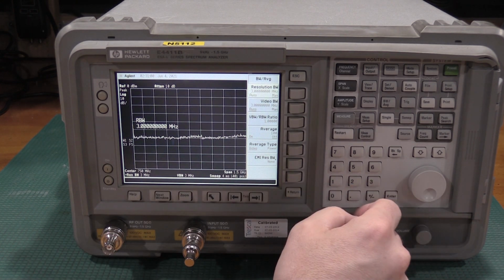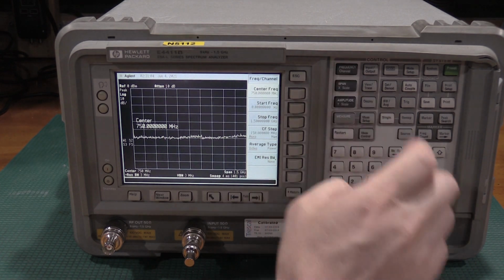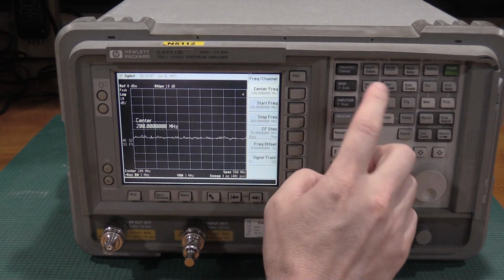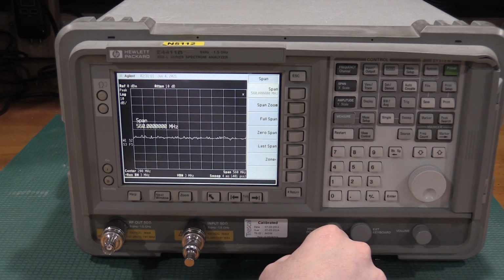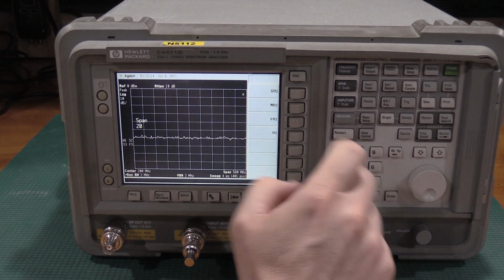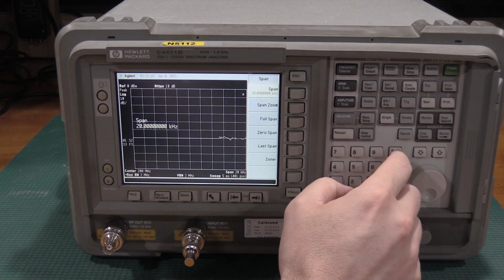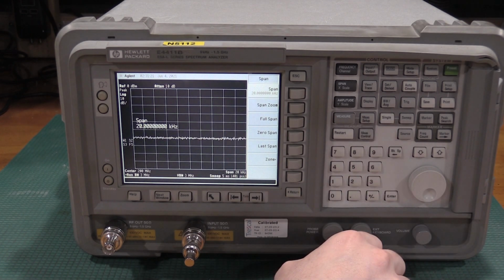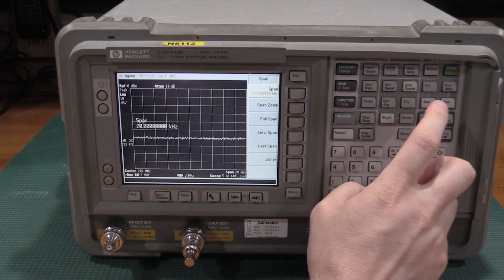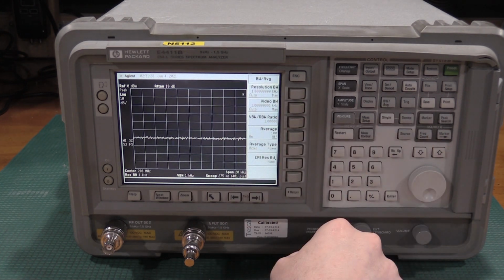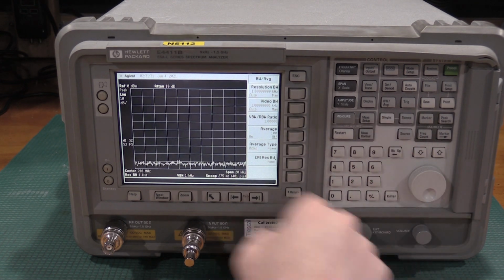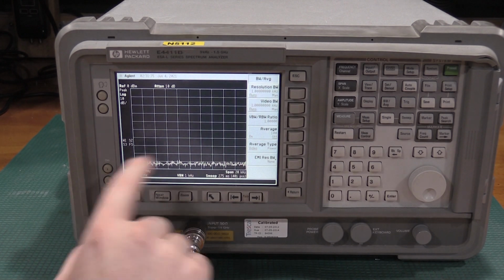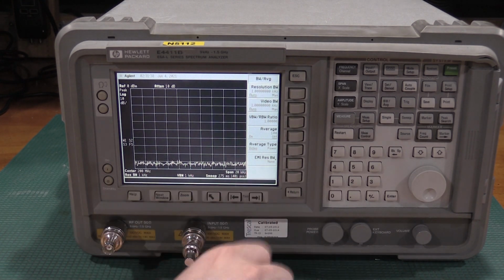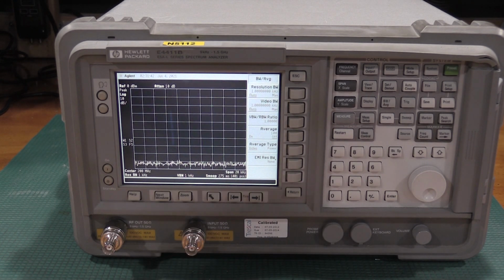But if I go to, let's call it 200 megahertz, so frequency 200 megahertz, span of 20 kilohertz, sweep. When we do that, we can change our bandwidth to 1 kilohertz, and we can do a sweep, and our noise goes way down because we're sweeping. So we get our 1 kilohertz bandwidth, but it's still 275 milliseconds, but it's fast. So, given that I have my frequency generator set to 200 megahertz at a negative 10 dBm signal.